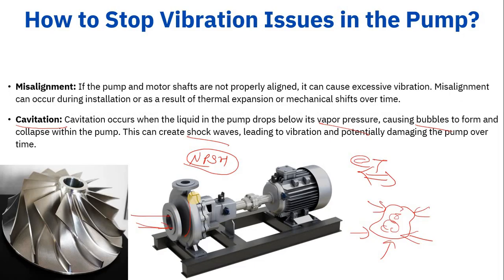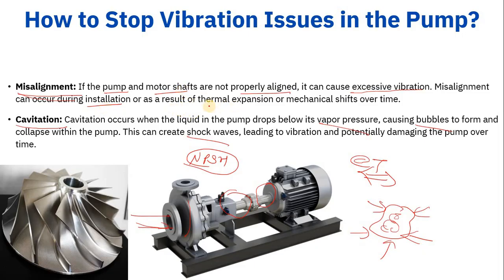The next cause is misalignment. Misalignment means the pump shaft and motor shaft are not properly aligned. If they are not aligned correctly, it can cause excessive vibration. Misalignment can occur during installation, during scheduled maintenance, or as a result of thermal expansion or mechanical shift over time.